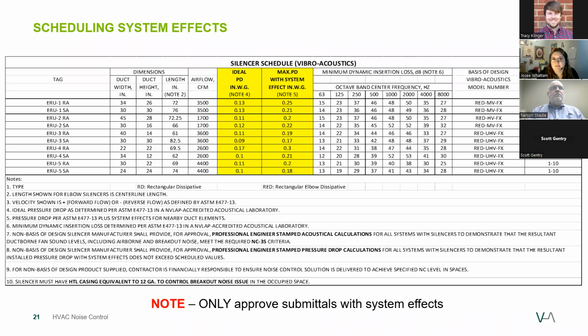We also recommend specifying PE stamped calculations, which we can provide to fully eliminate your risk. A quick note to avoid potential pressure drop issues later in a project is to only approve submittals where system effects are shown.